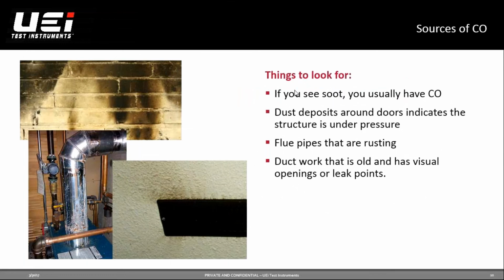If you have a cracked heat exchanger, take a look at that wall. Looks pretty awful, you can see the soot all over it. If you look down by the door and start seeing dust deposits around it, it can be a very good indication that the structure is under pressure. Looking at those flue pipes, you see rusting going on, you want to get those changed out because we all know what happens with rust. Eventually it eats through and allows all of that CO that should be getting vented out of the house to start exposing itself within the house.